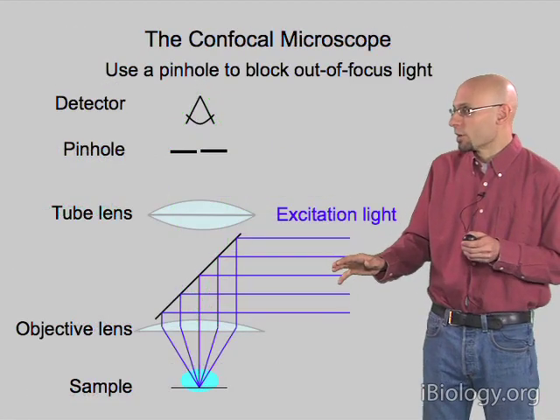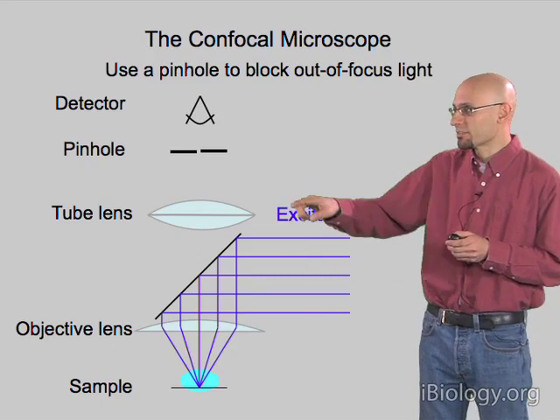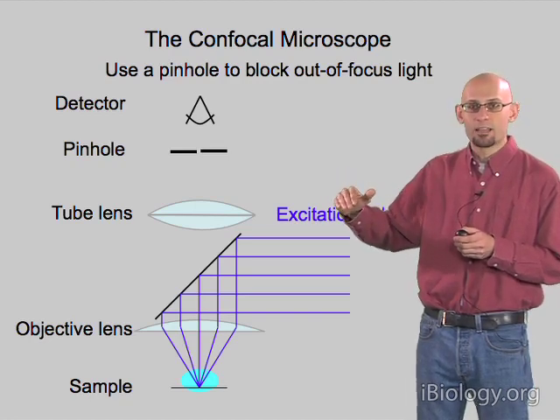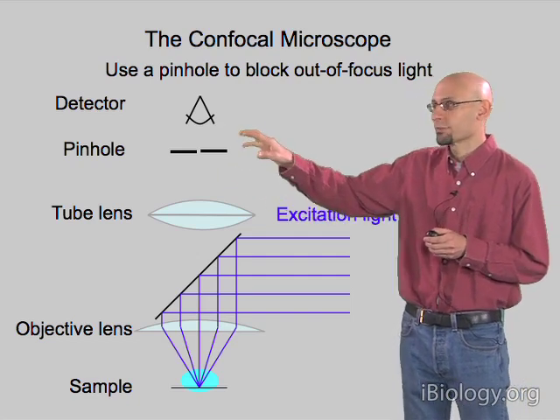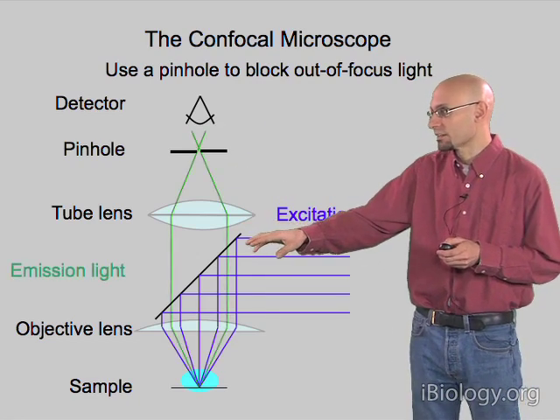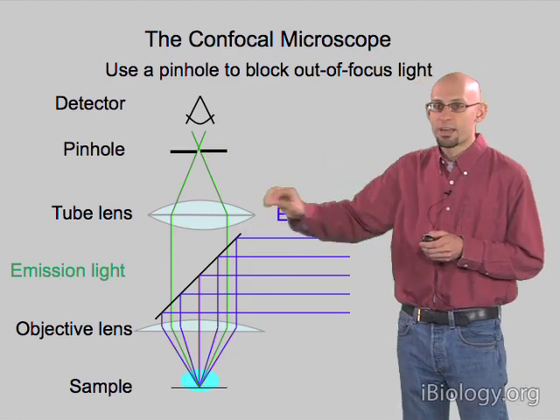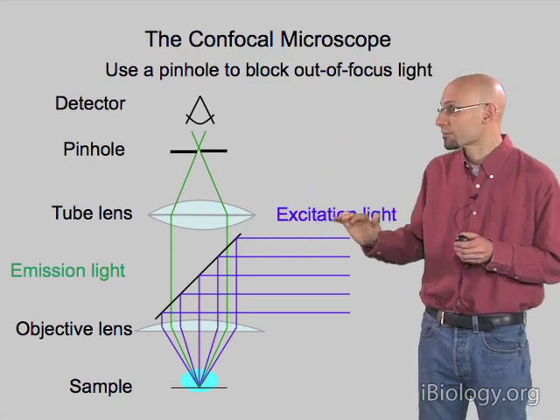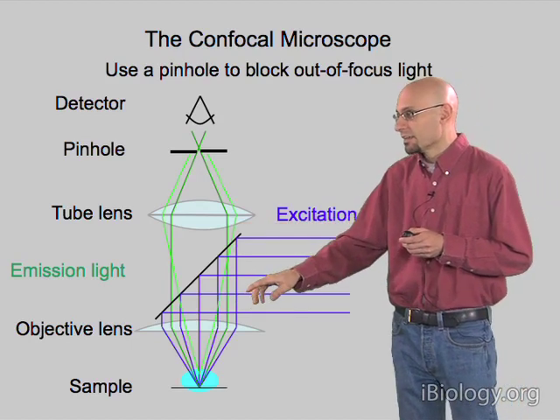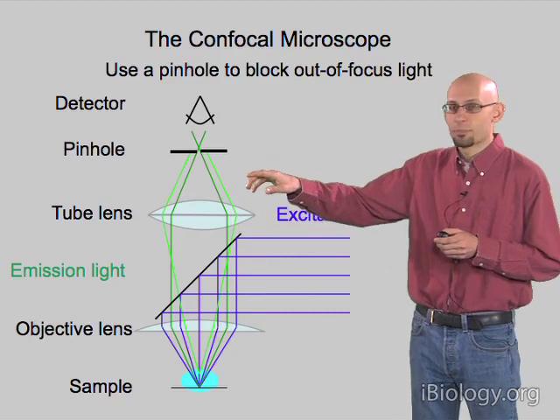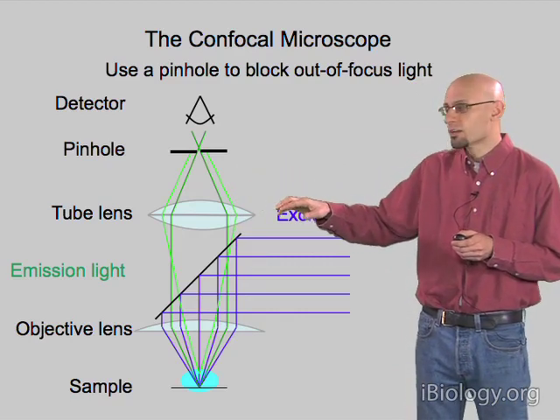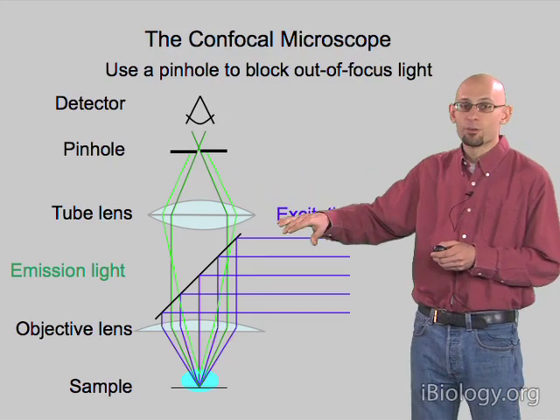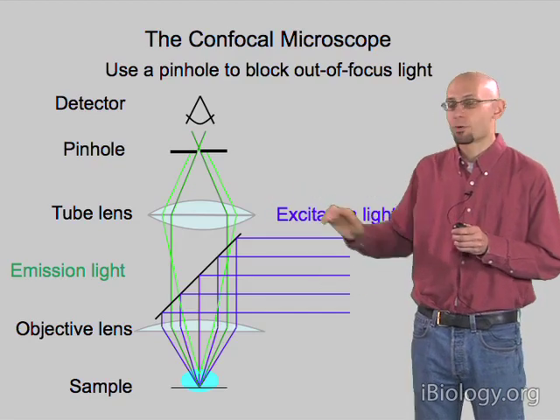The trick in a confocal microscope is to physically block that out-of-focus light by replacing our camera with a pinhole, placed such that it exactly passes the light that's in focus. That light will come to a focus at that spot, make it through the pinhole, and reach the detector. The corresponding out-of-focus light will make a big fuzzy disk on the pinhole, which will block the majority of that light and prevent it from reaching the detector. So now we've arranged our microscope to only see the in-focus information.